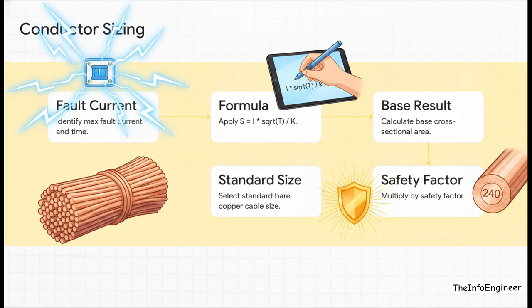To size the buried copper conductor for your grid, you calculate it exactly. Say you have a maximum fault current of 20 kiloamps that needs to clear in 1 second. You apply the standard formula using a material constant of 115 for bare copper. That gives you a base of 174 square millimeters. Then, you always add a safety factor of 1.25, which brings us to 217.5.